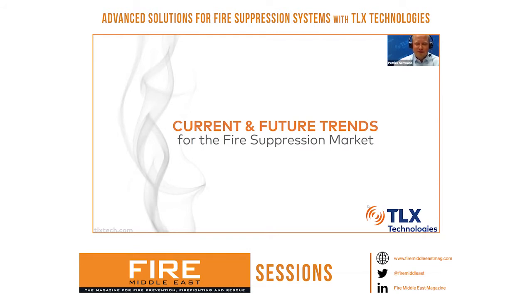This is an advantage when it comes to system inspections and maintenance checks. Most fire systems require a semi-annual inspection to verify proper electrical actuator function, as well as proper levels in the suppressant tanks, at least at a minimum. With the ability for smart devices to send that data to the fire control panel, the system manufacturer can provide that data real time to the customer via a web interface or other human interface.